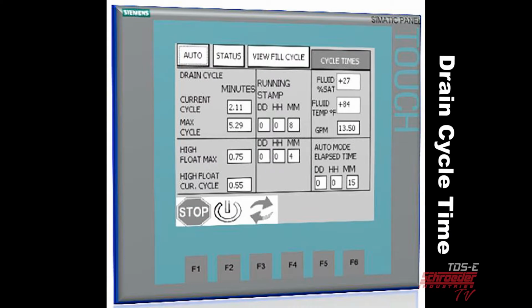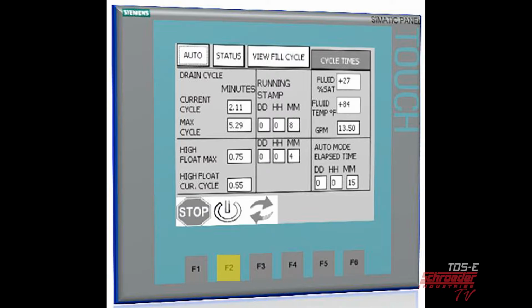The read-only drain cycle time screen displays the drain cycle time information in minutes. Similar to the saturation history, the longest cycle time is marked by a running timestamp, which is the elapsed time of the current cycle. In addition, the time during the drain cycle when the high float switch is energized is recorded. All information is retained until a new auto mode cycle is started by pressing the hard key F2, but if the power is lost, the data is also reset. Identical information is stored for the fill cycle on a separate screen.